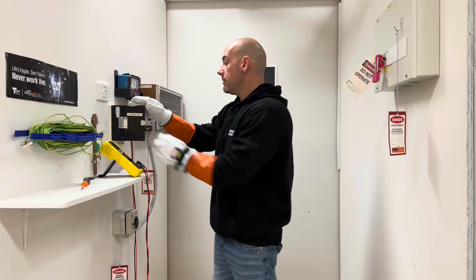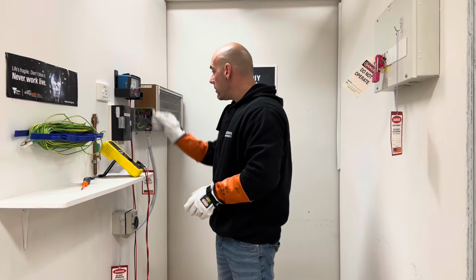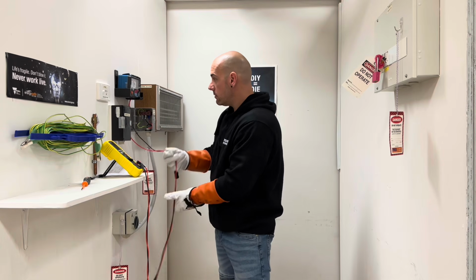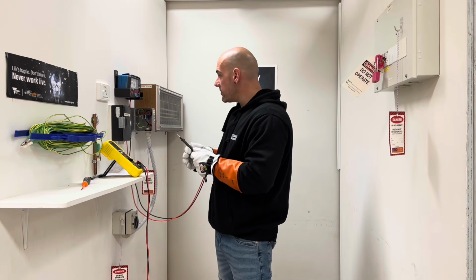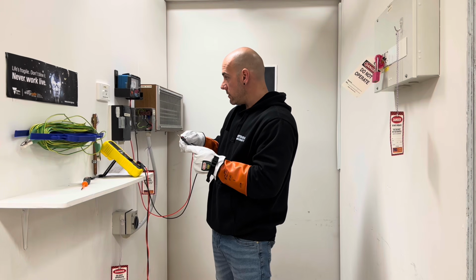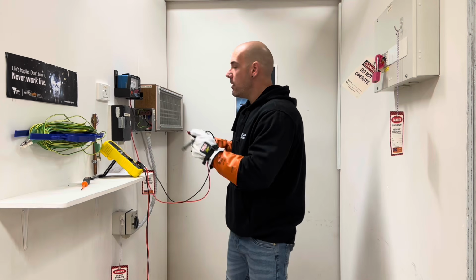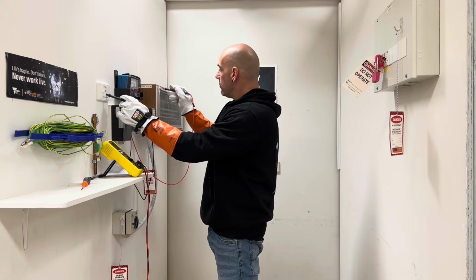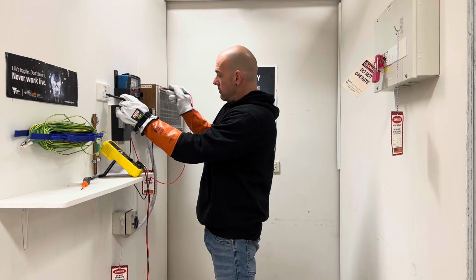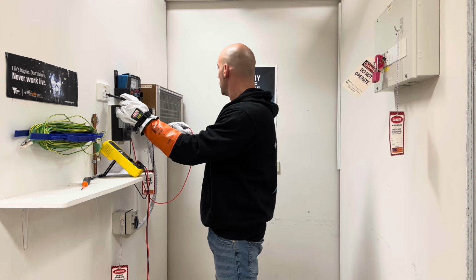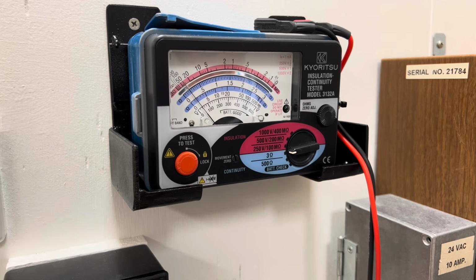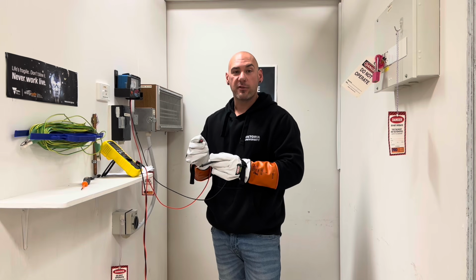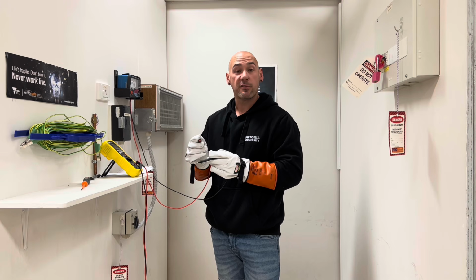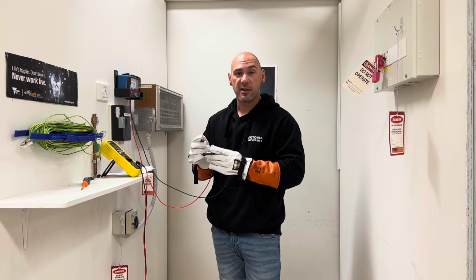Okay. Now we will be doing an earth continuity test. So put our meter on and do a battery check. Okay, good. Go to the 3 ohm scale and we short our leads out, and our meter is reading 0, which is great. And we go from the reference earth to the frame of the appliance. Great. So I've just measured 0.1 of an ohm, which is less than the maximum resistance value of 0.5 of an ohm, which indicates the earthing system is a pass.